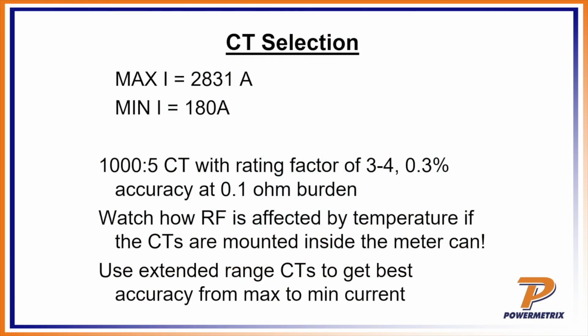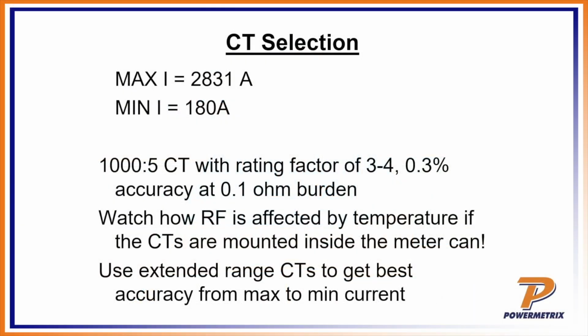Use extended range CTs to get the best accuracy at max and min. So remember, if we have the extended range, it's going to go all the way back and grab them, right? So it'll go on 1,000 to 5. If I have an extended range, remember the 5%, it'll go all the way down to 50, okay? So I can go all the way down to 50 amps, so I definitely cover my 180 on the min side, right? So if I have a 1,000 to 5 CT with a rating factor of 4 and I have extended range, then I should be in good shape.